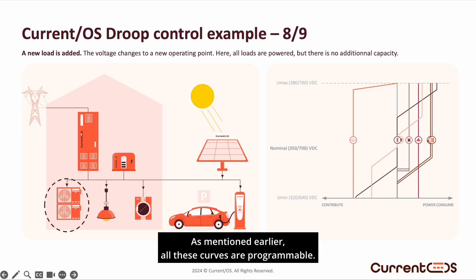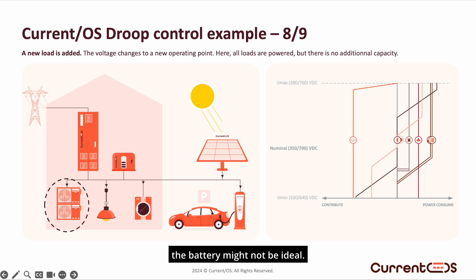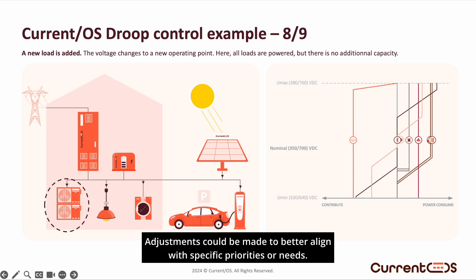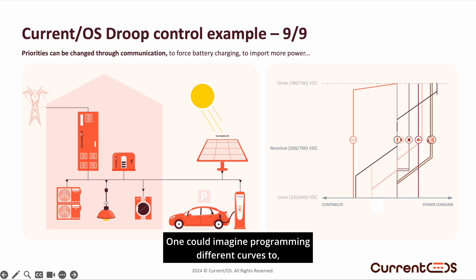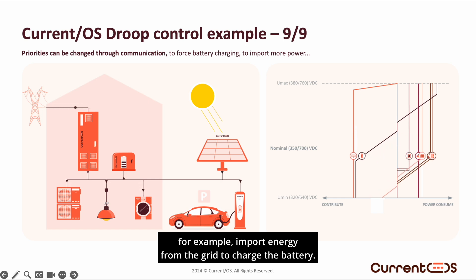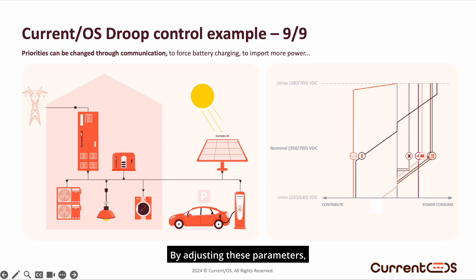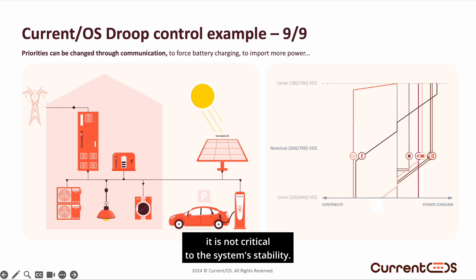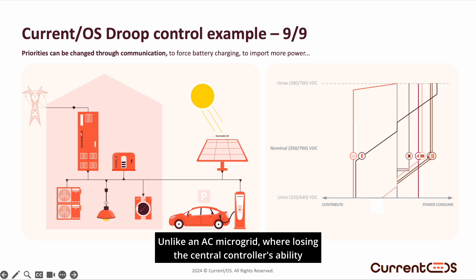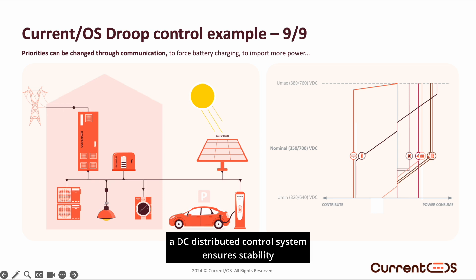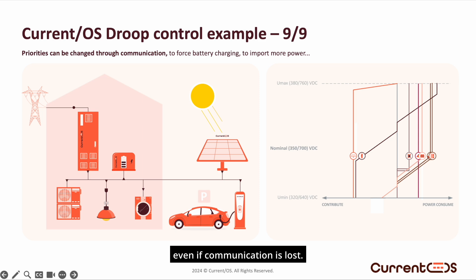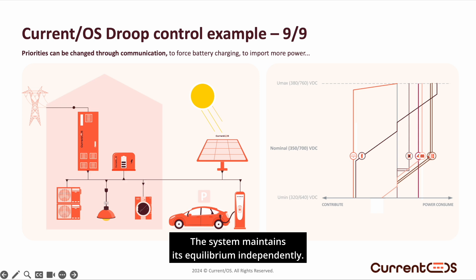As mentioned earlier, all these curves are programmable. In this example, not being able to recharge the battery might not be ideal — adjustments could be made to better align with specific priorities. One could imagine programming different curves to, for example, import energy from the grid to charge the battery. While communication is used to modify these parameters, it is not critical to the system's stability. Unlike an AC microgrid, where losing the central controller's ability to manage current sensors, contactors, or converters can lead to instability, a DC distributed control system ensures stability even if communication is lost. The system maintains its equilibrium independently.